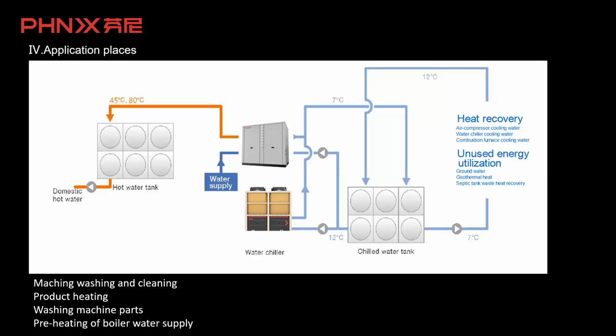So, Troy, do you have anything to say about this application? If I understand it correctly, you mean the water source can be working together with the water chiller, the unit below. Yes, they can work together to produce the cold water, like 7 degrees, installed in the chiller water tank. Then the cold water is provided from the tank to the indoor side, then goes back to the tank, then goes back to the unit.